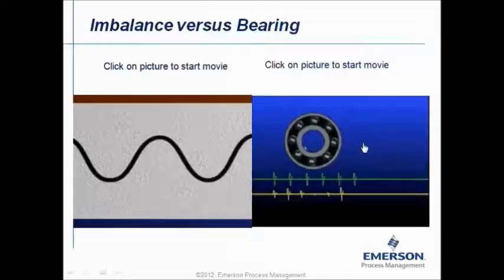Now the power of those two short animations is that everybody realizes and understands immediately that two different mechanical problems create two different kinds of vibration signals. In reality, we will of course do the opposite. We will measure this signal or this signal, and then it's up to the person doing the analysis to make the link with a mechanical problem, an imbalance or a bearing.